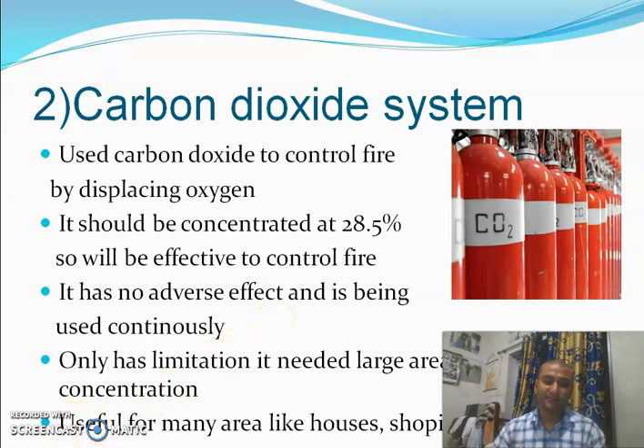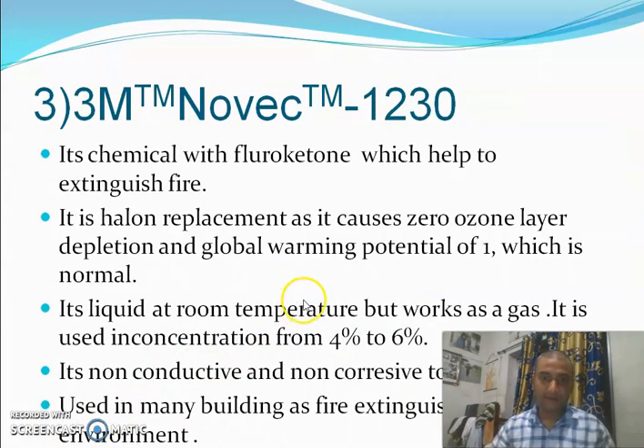Now moving to the next topic: 3M Novec 1230. It's a chemical, a fluoroketone, which helps extinguish fire. It's a halon replacement as it causes zero ozone layer depletion and has a global warming potential of 1, which is normal. It's liquid at room temperature but works as a gas, used at a concentration of 4% to 6%. It is non-conductive and non-corrosive too.